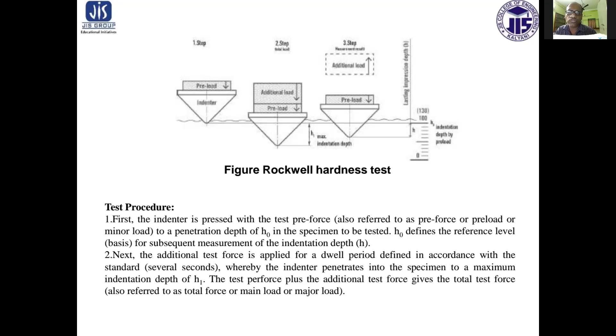After the dwell period, the additional test force is removed. The indenter moves up by the elastic proportion of the penetration depth under the total test force and remains at the level of the residual indentation depth. This is also referred to as the depth differential. Now, the Rockwell hardness can be calculated using the residual indentation depth and a formula defined in the standard, taking into account the applied Rockwell scale.